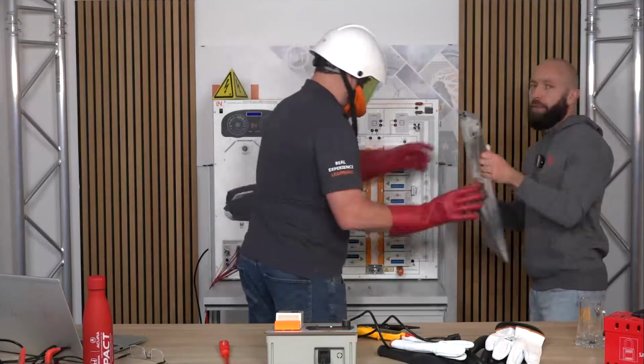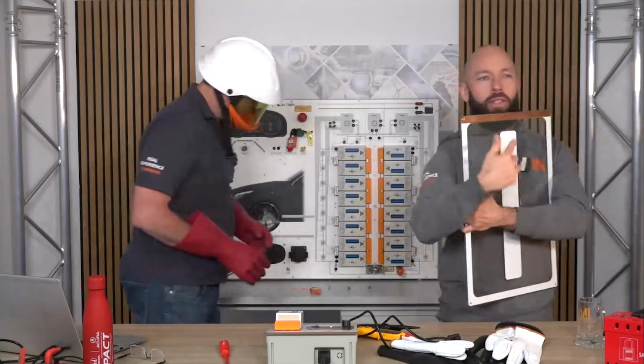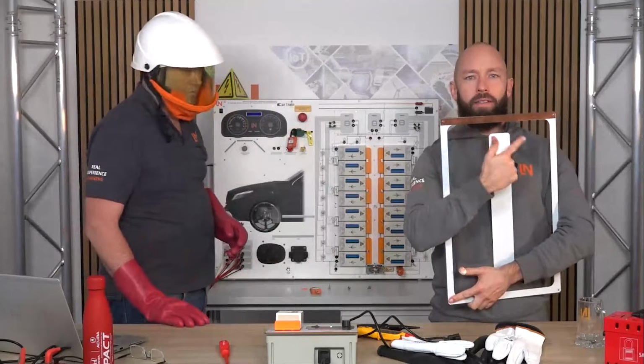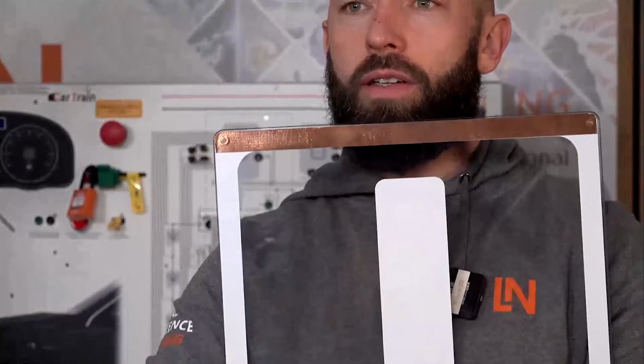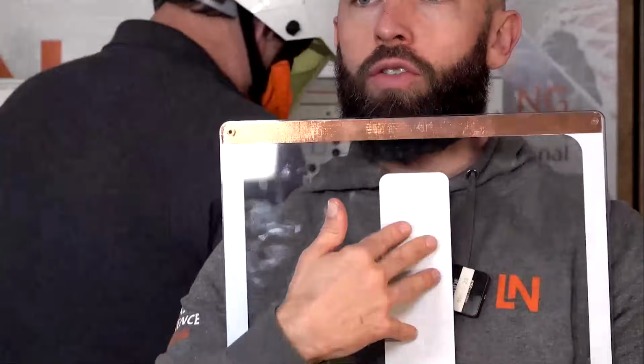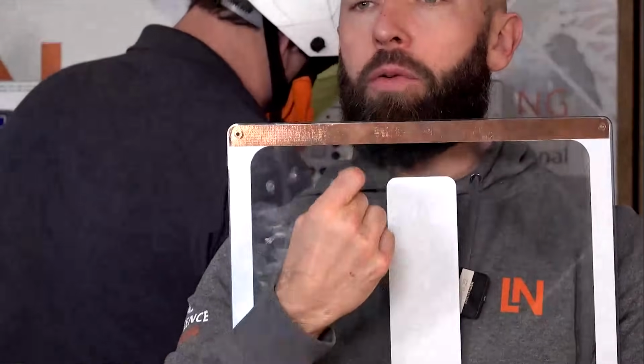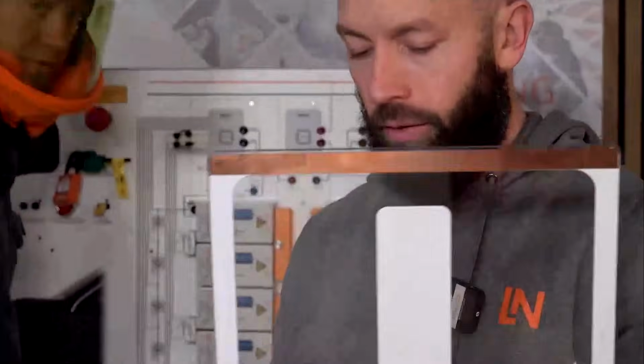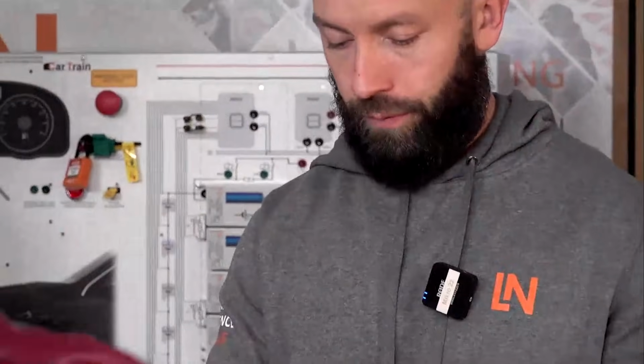Daniel has done it quite a few times now, so it goes fast. I take off the cover, and this is also where you see the connection for the interlock. As soon as this is lifted and the electric connection is interrupted, we get an interlock fault.